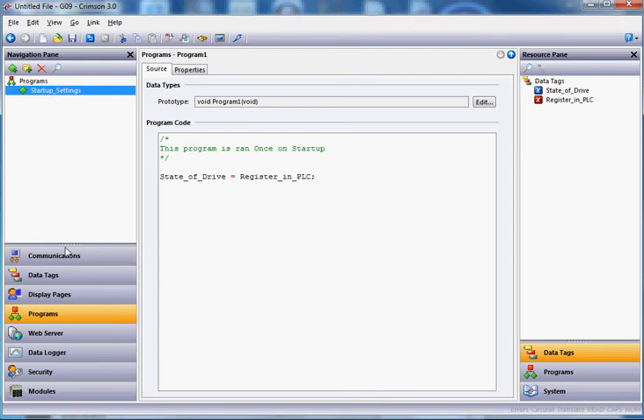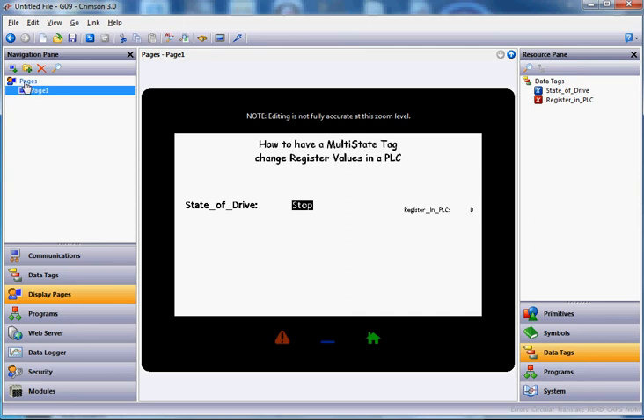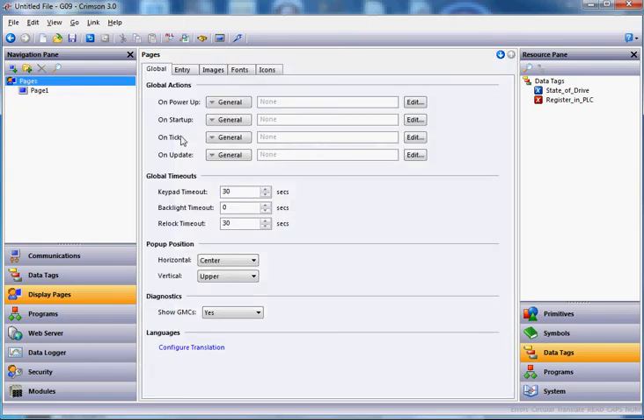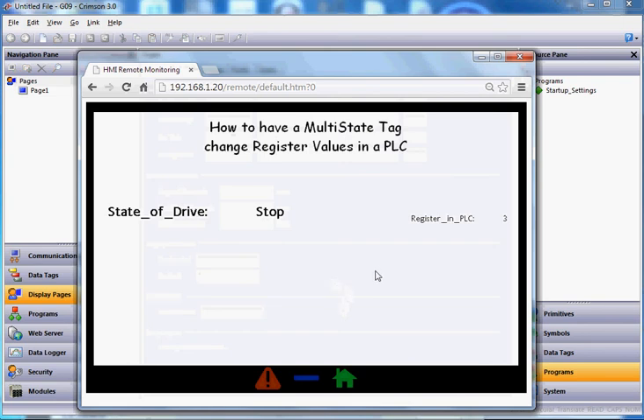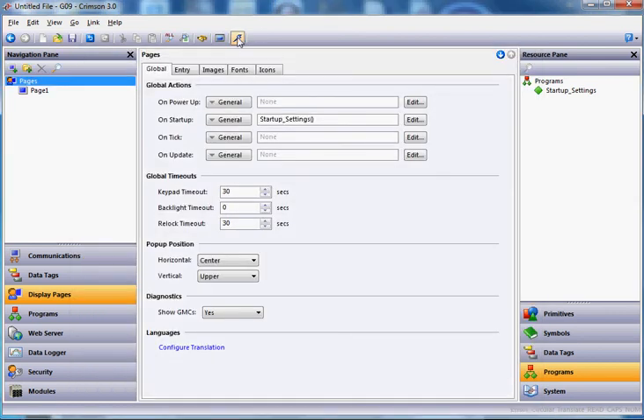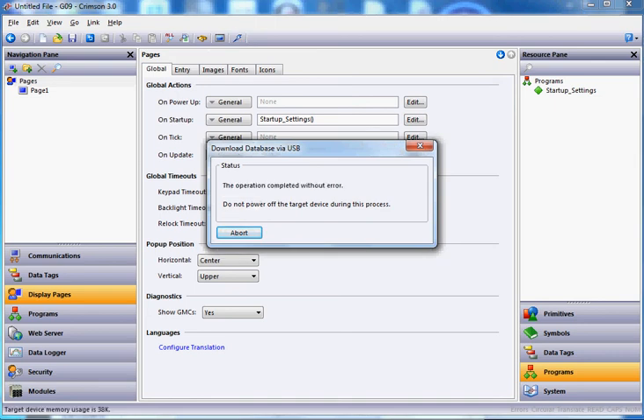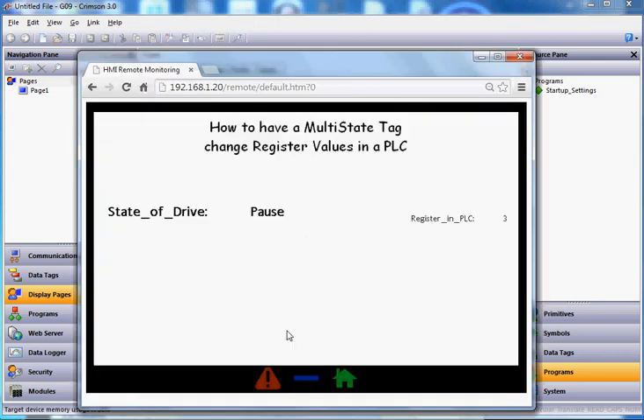I want that program to run once on startup. I'll go back to Display Pages on the left and click on the word Pages up top. Under the Global tab, there's an option to run a program once on startup. I'll go to Programs on the right side, drag the Startup_settings program out, and drop it in that field. To verify it works — here's the HMI currently showing stop, but the PLC is actually in pause mode because the register is three. I'll download, watch what happens — boom, it started up automatically in pause mode because it went out and read the PLC register first.